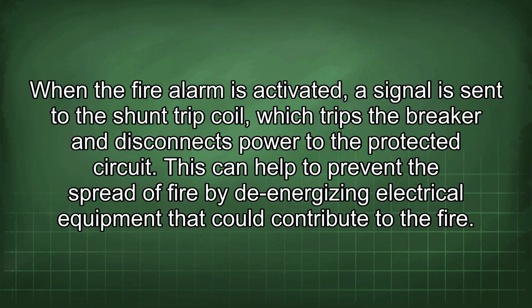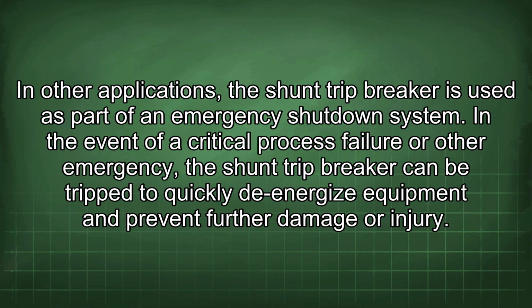When the fire alarm is activated, a signal is sent to the shunt trip coil, which trips the breaker and disconnects power to the protected circuit. This can help to prevent the spread of fire by de-energizing electrical equipment that could contribute to the fire. In other applications, the shunt trip breaker is used as part of an emergency shutdown system. In the event of a critical process failure or other emergency, the shunt trip breaker can be tripped to quickly de-energize equipment and prevent further damage or injury.